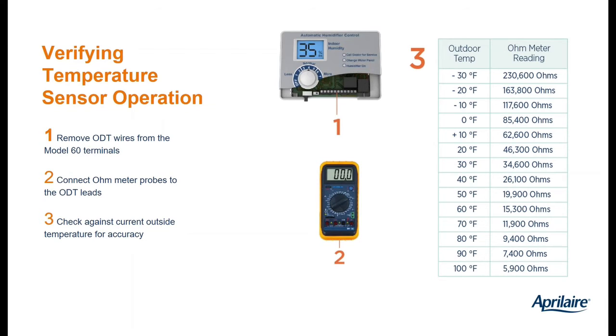Because the key to the automatic humidistat is it measuring the correct outside temperature, before you wire the outside temperature sensor to the thermostat, it's always a great idea to grab your multimeter and just ohm it out. So, grab your smartphone, see what the outside temperature is for this zip code, ohm it out. This table is in the installation instructions, and you can see, for example, let's say it's 20 degrees outside, you'd want to see about 45,000, 46,000, 47,000 ohms. Again, if we're plus or minus 5 degrees, that's perfect.